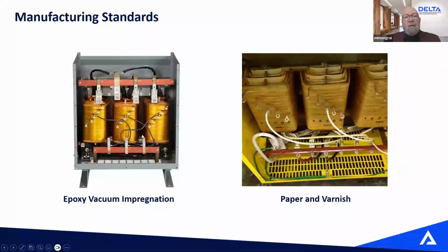So when you open the panel, this is a typical low voltage transformer we build at Delta. Some of our low-cost competitors use what we call the paper and varnish technique. Mainly they will build the windings, the coils themselves, and before putting the coils on the transformer leg, they will either spray the windings with varnish or manually take the coil and dip it in a drum of varnish. So you're going to have varnish on the outside of your coils, but within the coil, when you look at the winding from the top, it's all layers. You have no protection material. You have no varnish. So when you expose those types of transformers to humidity or a harsh environment, they will fail quite rapidly compared to a transformer that's been protected by epoxy.